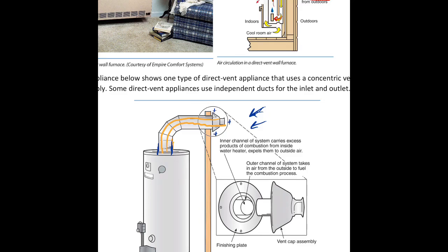Those are typical of systems that would be, you know, even your tankless water heaters. This one here is a tank type water heater. The key thing to making these work is you must absolutely have the intake air and the exhaust air connected directly to the dedicated portions on that appliance or they will not work consistently and you'll have problems with flames pushing back if it can't be in the right pressure plane.